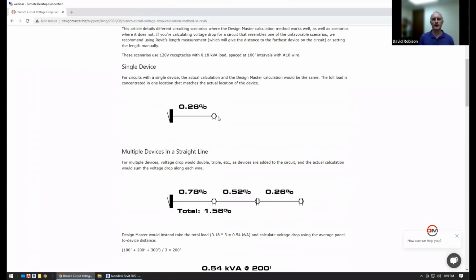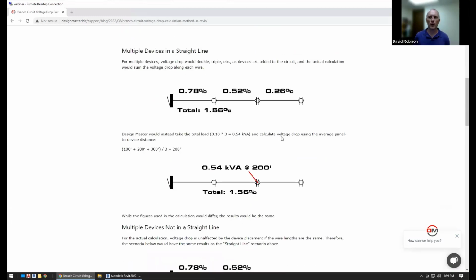In this case, it's 100 feet away. It's a standard receptacle with 0.18 kVA assumed on it. And we end up with a 0.26 voltage drop. So for a single device, that's what you get for the voltage drop. If you have a single receptacle, a single piece of equipment, it's a fairly straightforward calculation, and our branch circuits are going to be spot on. When you have multiple devices is where it becomes more complicated.